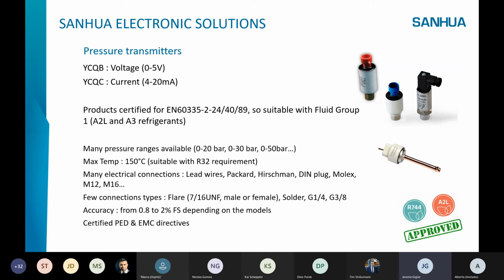So we have many pressure ranges available now. We have 0-20 bar, 0-30, 50, or 0-16. We have a lot of models in the catalog now. The maximum temperature is 150 degrees, so it is very suitable for a discharge line with R32, for example, because R32 needs to handle a very high temperature in the discharge pipe.